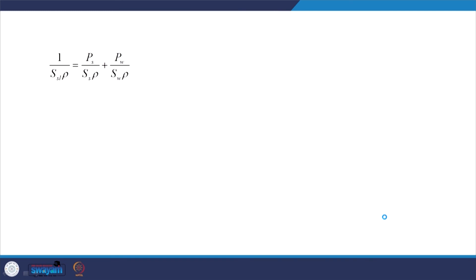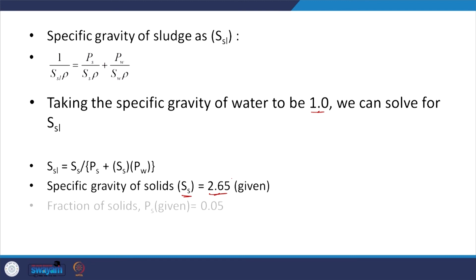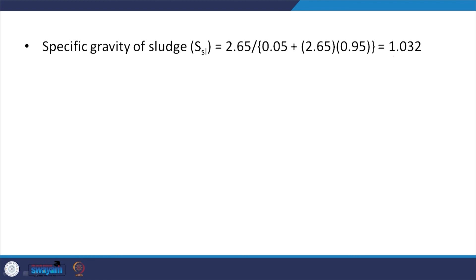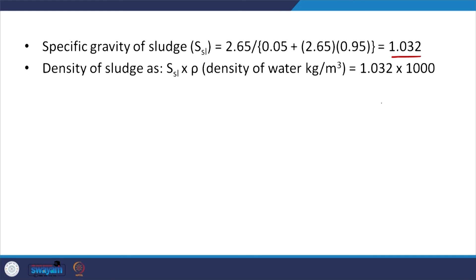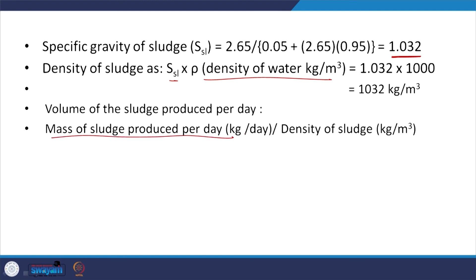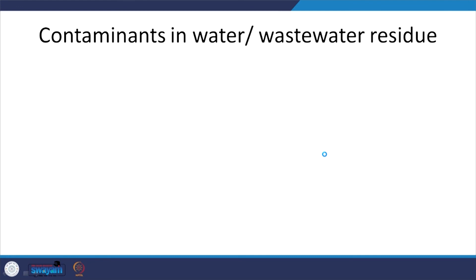This is one of the equations we looked at earlier, and we have most of the relevant variables. Taking the specific gravity of water to be 1, we have the relevant equation. Specific gravity of the solids is given as 2.65, and PS and PW are also given — 5% solid means 95% water. Plugging it in, the specific gravity of sludge is 1.032 — slightly higher than that of water, denser than water. Density of sludge equals specific gravity times density of water. So, volume of sludge produced per day equals mass of sludge divided by density. With the mass of sludge produced and the density calculated, the volume is approximately 41.5 m³ per day.